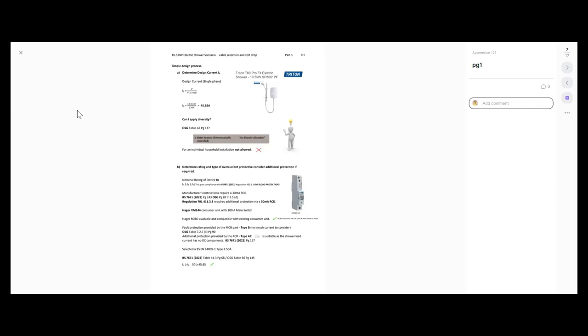The overcurrent protection side of this RCBO — the MCB part — we're going to go with Type B, because we've got no inrush current to consider. It's just a purely resistive load. Last week we had a look at applications of circuit breakers Type B, C, and D — we can find that in the on-site guide table 7.2.7 on page 90. Because it's a standard circuit with standard load, a Type B will suffice.